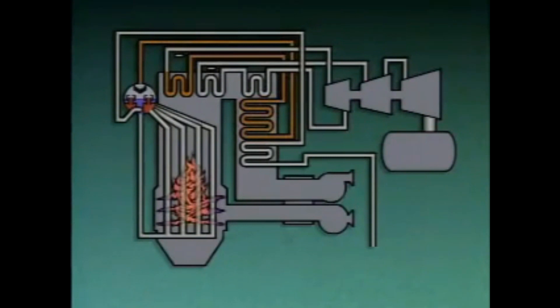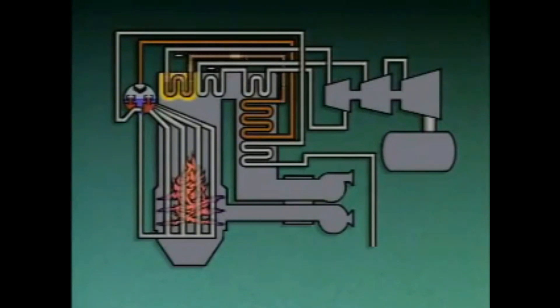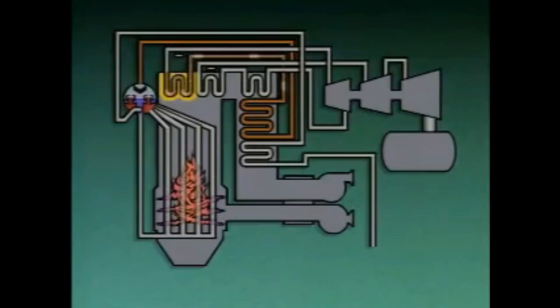The primary superheater is designed to raise the temperature of steam from its saturation temperature to a specific temperature range. The secondary superheater raises the temperature of the steam again. The secondary superheater is usually located closer to the boiler furnace so that it is exposed to higher temperatures. The secondary superheater may be either a convection superheater or, as in this case, a radiant superheater.